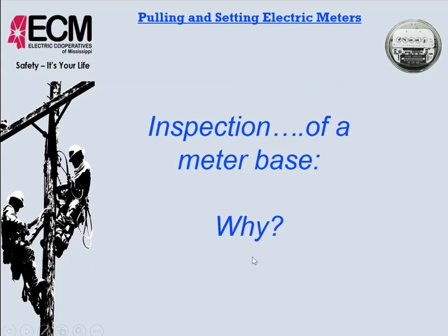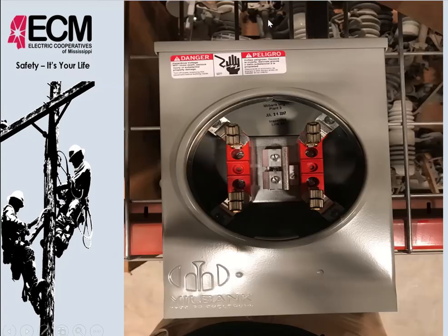Okay, so, inspections of a meter base. We're going to run through these fairly quickly and show you a couple of things that typically could be found while inspecting a meter base. This one right here has a band inside. The band is what connects the meter to the meter base lid, and it's on the inside. If you were to make this hot, it probably would touch these, or had the potential to fall down across these two and short them out. So I want to make sure that you get that out of there.